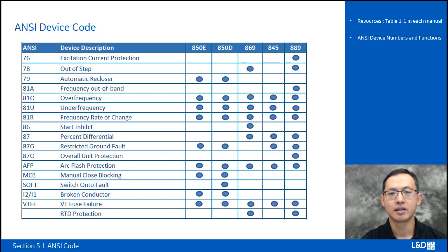The 850D is used for the utility, so it has a protection called switch on fault, SOTF. Then another element at the end that doesn't belong to any ANSI number is VTFF, the VT fuse failure. This table is generated from the version 2 of the 8-series manuals. So that's the resource. Because the firmware keeps updating, these functions may change, so always go to the latest manual and refer to the latest functions to get the accurate table. This is only accurate for version 2. There is also another ANSI device number table you can download from the GE Grid Solutions website.